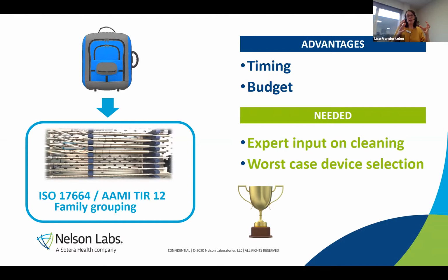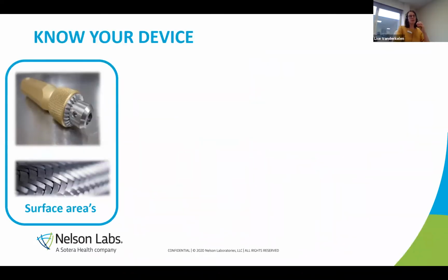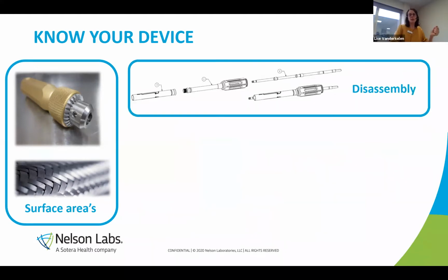It will reduce cost. What you need is an expert input on how you are going to group your families, but also from a cleaning point of view. So you're going to need that expert input, and you're going to select worst case devices. Now, once you have your devices on which you want to perform your cleaning validation, you need to know your device. You need to look at what the surfaces and the areas are which are difficult to clean. Where are holes? Where are gaps? Where can soil intervene?